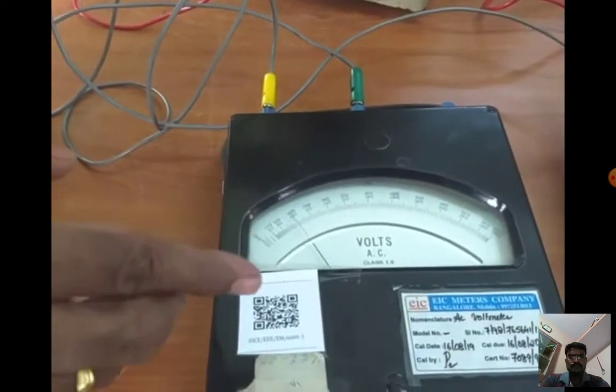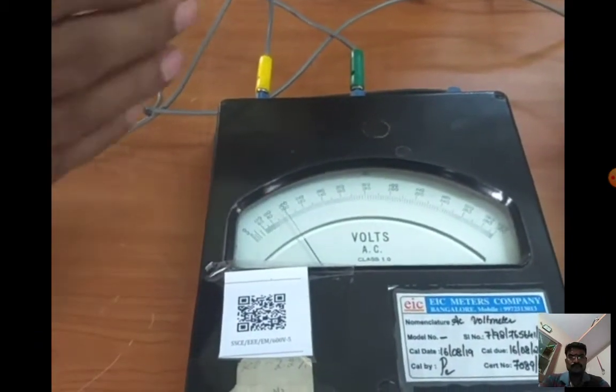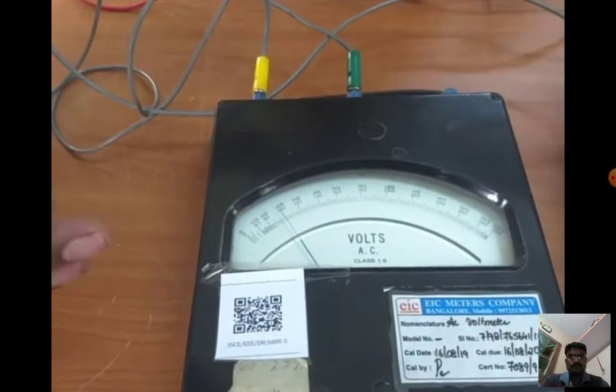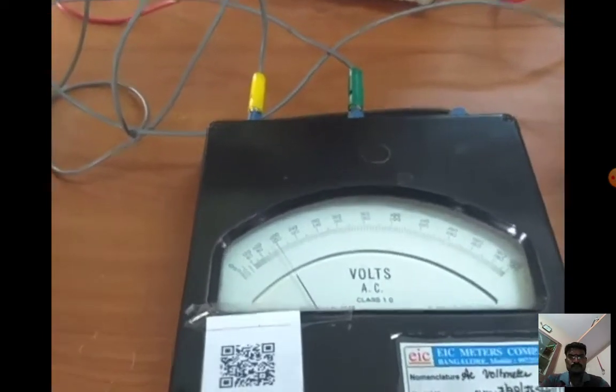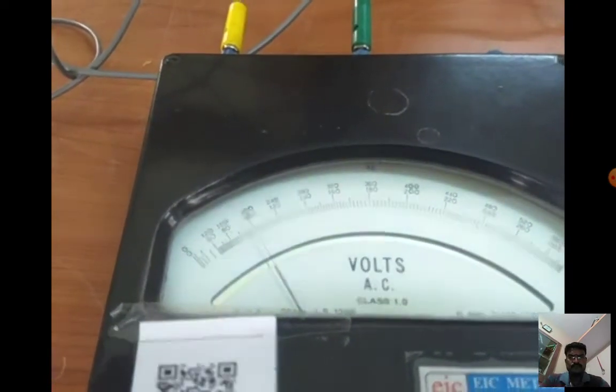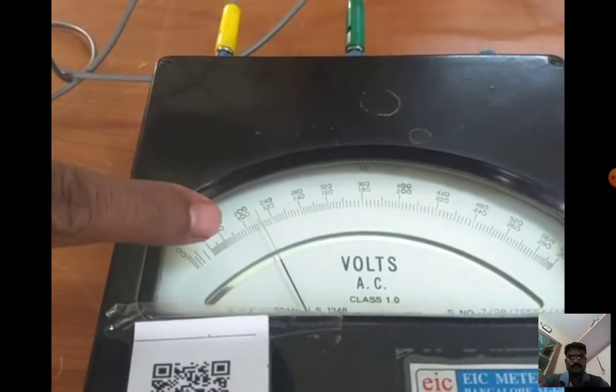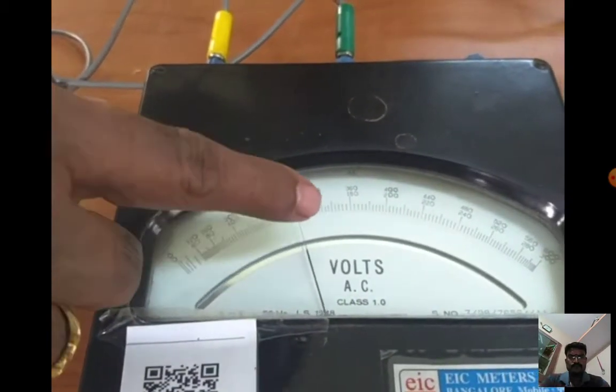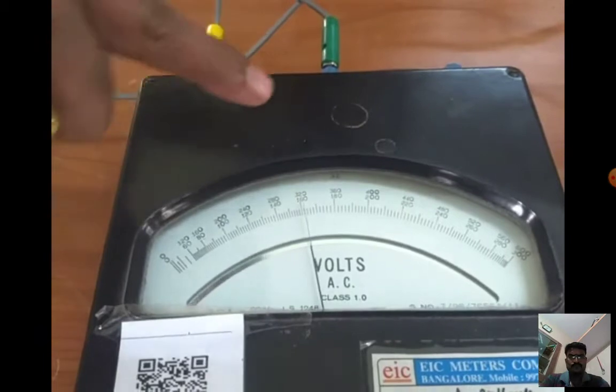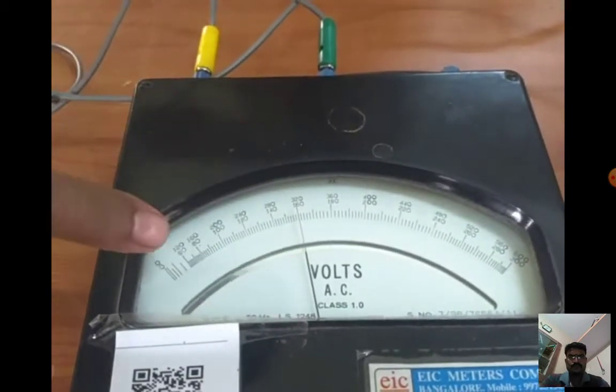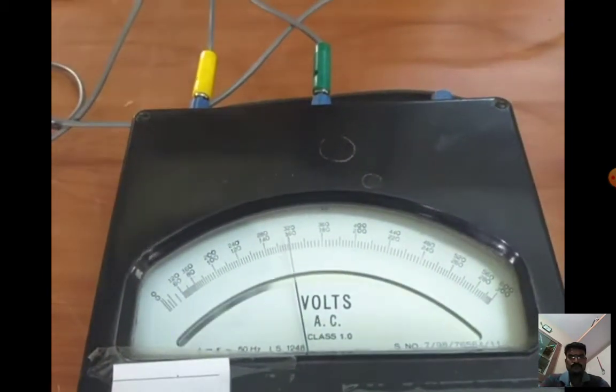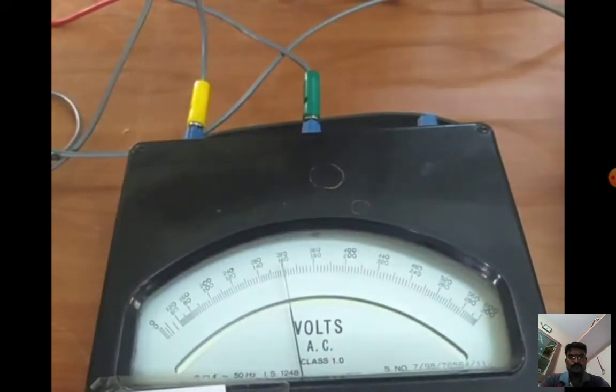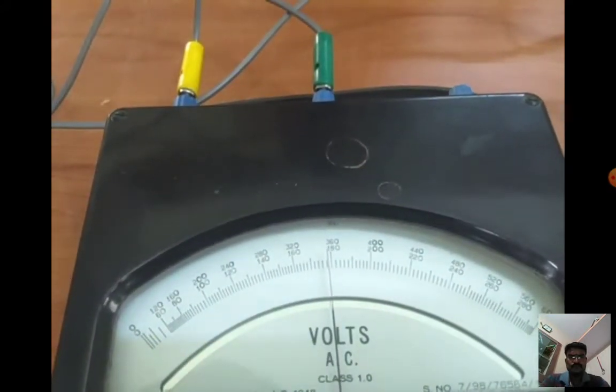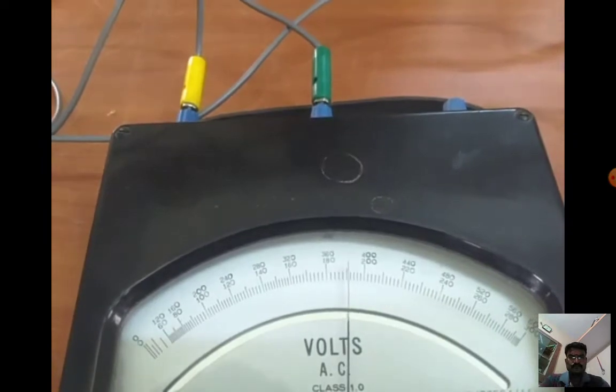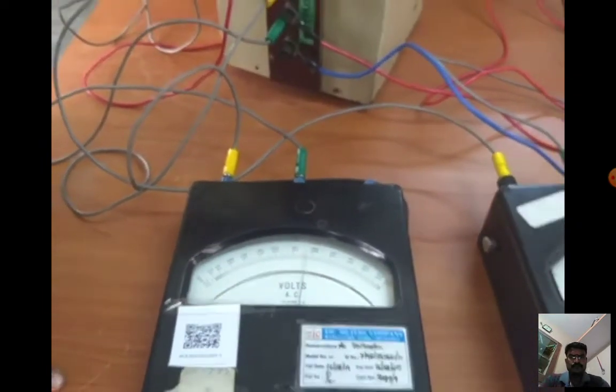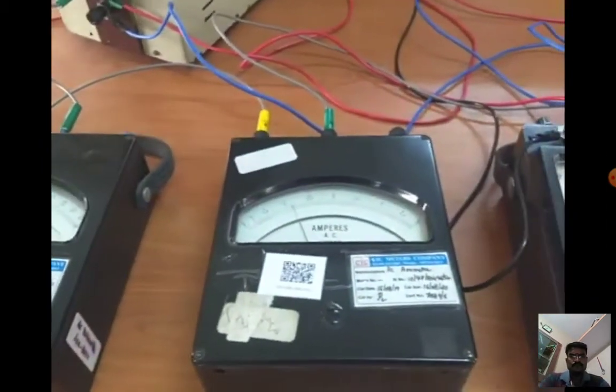because the voltage we are measuring here is between the lines, the R and B line or the R and Y line. So the voltage should be 380. Here we connected to the 600 range, so the upper value we should take. Now the voltage 380 is given.